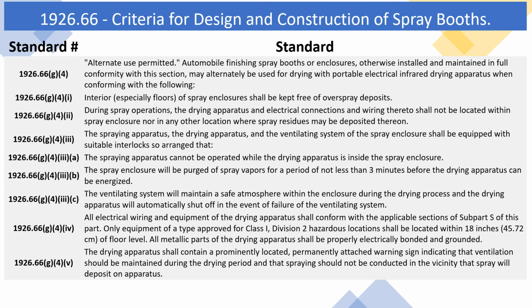1926.66 G4-3 The spraying apparatus, the drying apparatus, and the ventilating system of the spray enclosure shall be equipped with suitable interlocks so arranged that: G4-3a The spraying apparatus cannot be operated while the drying apparatus is inside the spray enclosure. G4-3b The spray enclosure will be purged of spray vapors for a period of not less than 3 minutes before the drying apparatus can be energized. G4-3c The ventilating system will maintain a safe atmosphere within the enclosure during the drying process, and the drying apparatus will automatically shut off in the event of failure of the ventilating system.